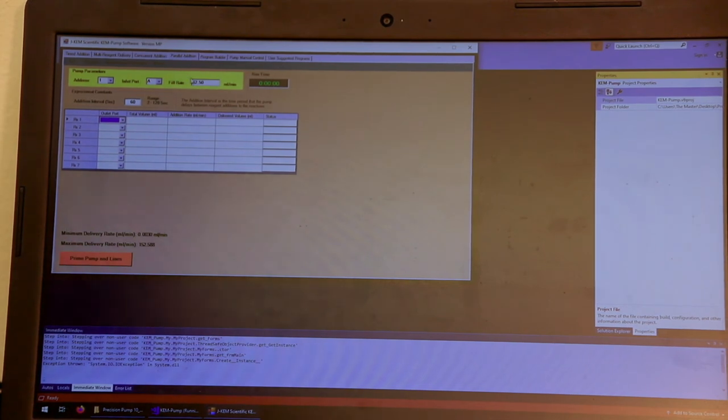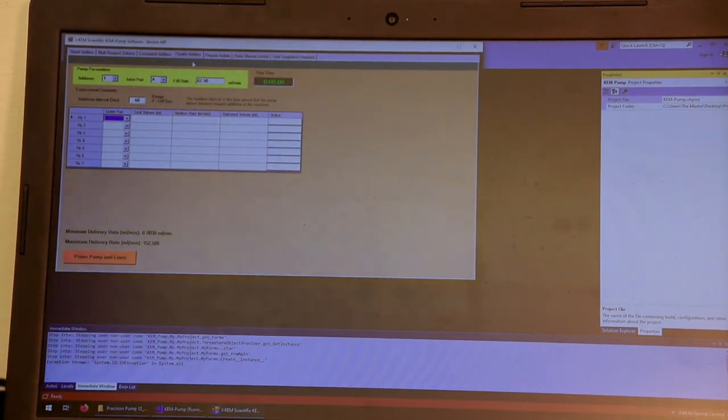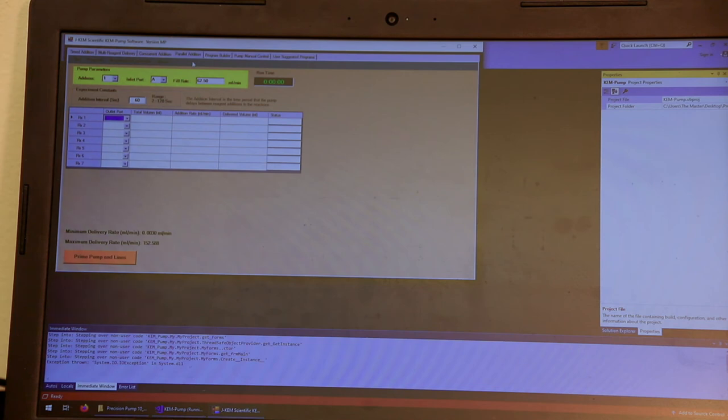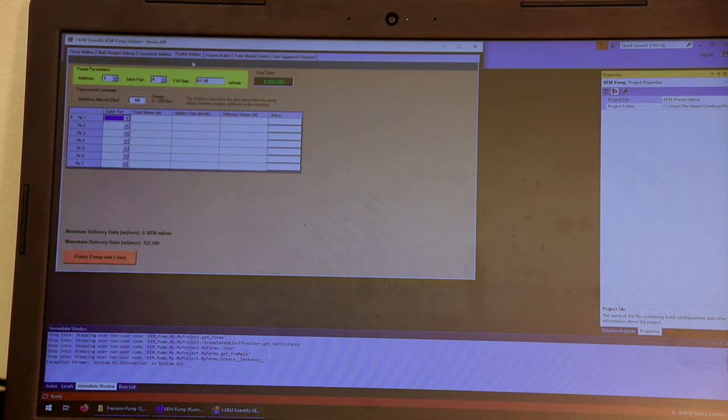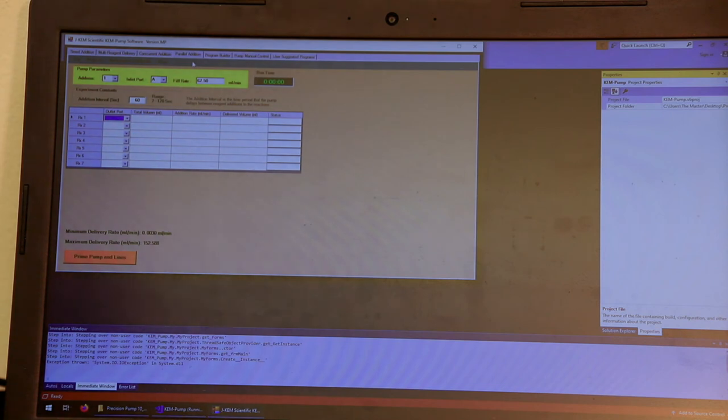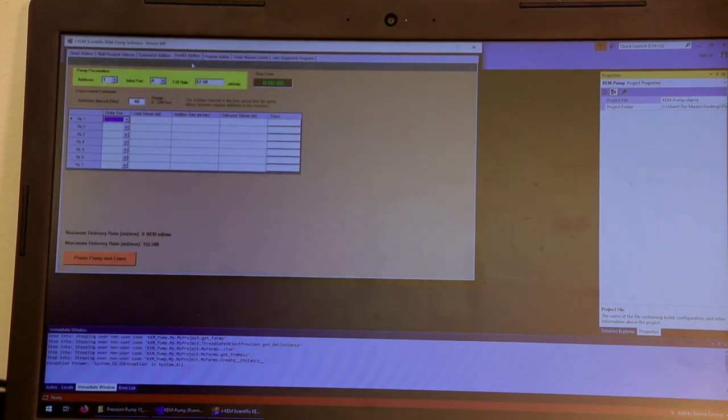This parallel addition experiment, what you can do if you have a single pump, you could use that single pump to add to multiple reactors. So with a single pump, you could say on port A is reactor one, on port B is reactor two, on port C is reactor three. And I want you to add 20 milliliters of my reagent at a rate of one milliliter an hour to reactor one. I want you to add 15 milliliters of the reagent at a rate of 10 milliliters a minute to reactor two. And then you could have a different volume at a different speed for reactor three. And so a single pump is able to add a common reagent or even different reagents to multiple reactors.